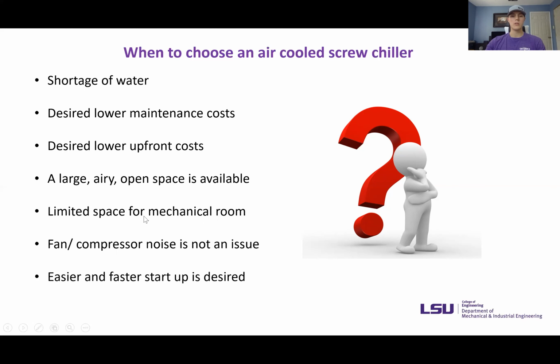If you have limited space for a mechanical room, so typically buildings downtown, the lots are very small and they can't just build an extra mechanical room, so they'll use an air-cooled screw chiller and install it on the top of the building. That way it's out of the way and they can still get their air conditioning. If the fan noise and compressor noise is not an issue, then you definitely want to choose an air-cooled screw chiller because you can just put it on top of the building and most likely not even hear it running. And they're also easier and faster to start up.